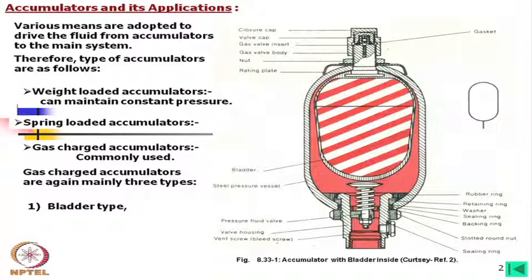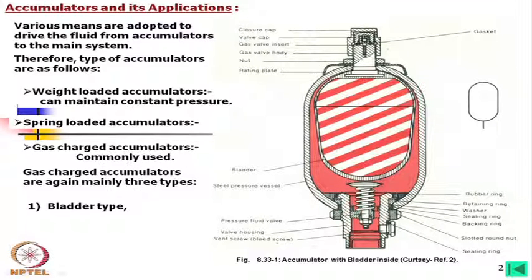Looking at the other details: there is a closure cap to protect the main valve cap and the total valve system. If you remove the closure cap, there is a valve cap, and if you remove that, there is a valve — basically a non-return valve — through which we can insert the gas. Then there is the valve body, fittings of the valve on the steel vessel, and a rating plate which by tightening makes it leak-proof with a gasket.